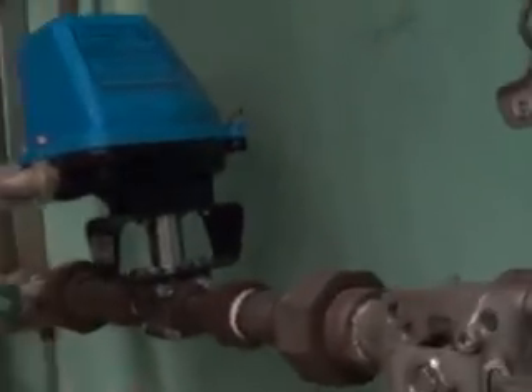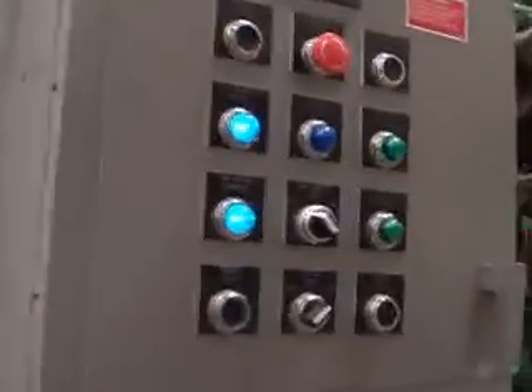This is a surface blow. It has a tendency to stick. We're making steam. Up above there is my sight glass, and we can see that on the graphic as well. I've shown you guys many times before, and since we're right here, take a quick peek in the firebox. I like to look at it myself. Now, it was colder during the night, so you can see how the refractory inside is glowing. But it is 40 degrees outside, and it is backing down. Actually, when I came in, it was 41. Last time I looked, it was 37.